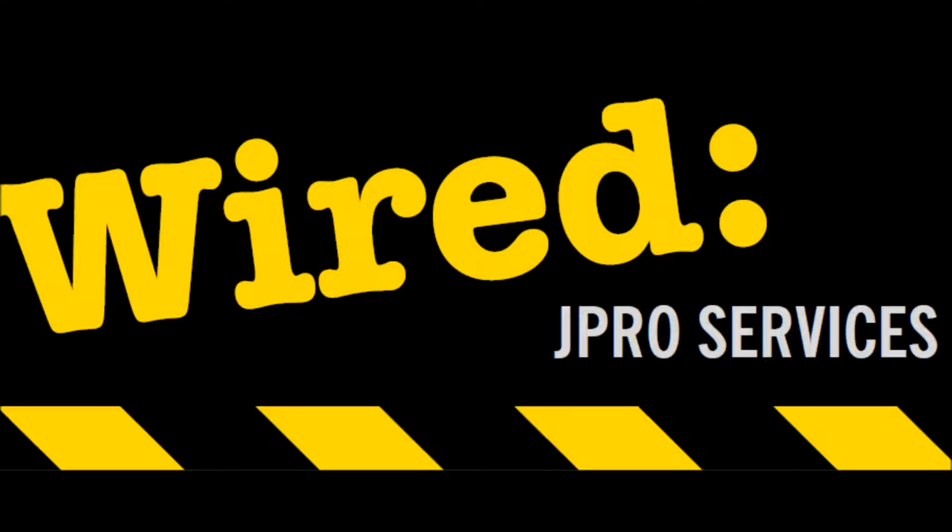Fire safety, as you heard about in Podcast 1, where we discussed fire risk assessments, depends on the potential risks and the different types of buildings, and this can create confusion. Also, as mentioned in Podcast 1, legislation requires that landlords carry out fire risk assessments in all areas of their properties. The law now states that private sector landlords since 1st of October 2015 are now required to have at least one smoke alarm installed on every storey of their properties, and a carbon monoxide alarm in any room containing a solid fuel burning appliance, for example, coal fires or wood burning stoves. After that, the landlord must ensure that the alarms are in working order at the beginning of each new tenancy.